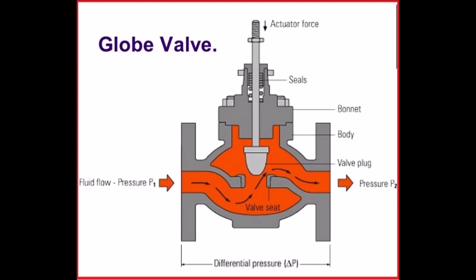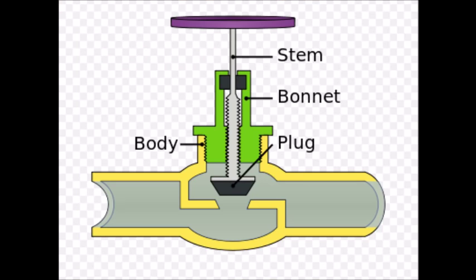Seat ring: The seat ring provides a stable, uniform and replaceable shut-off surface. Seat rings are usually held in place by pressure from the fastening of the bonnet to the top of the body. This pushes the cage down on the lip of the seat ring and holds it firmly to the body of the valve. Seat rings may also be threaded and screwed into a thread cut in the same area of the body. However this method makes removal of the seat ring during maintenance difficult if not impossible. Seat rings are also typically beveled at the seating surface to allow for some guiding during the final stages of closing the valve.